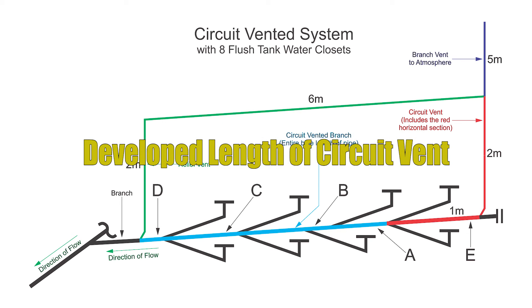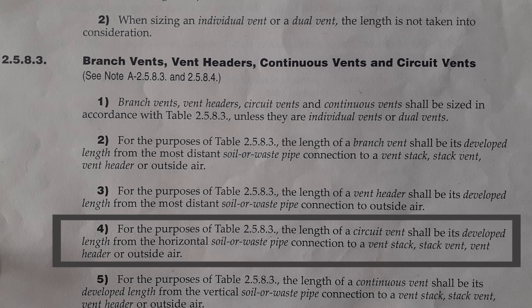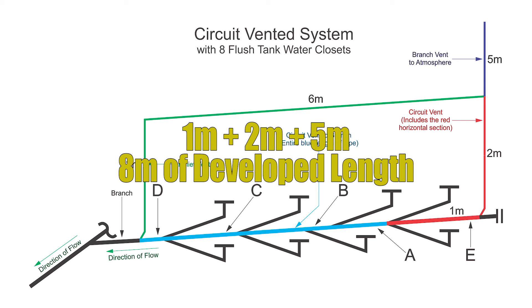The next part is the developed length. Code clause 2-5-8-3 part 4 states that for the purposes of table 2-5-8-3, the length of a circuit vent shall be its developed length from the horizontal soil or waste pipe connection to a vent stack, stack vent, vent header, or outside air. We start measuring from the first circuit-vented fixture and go all the way to outside air — in this example that equals 1 plus 2 plus 5 meters, giving us 8 meters of developed length.